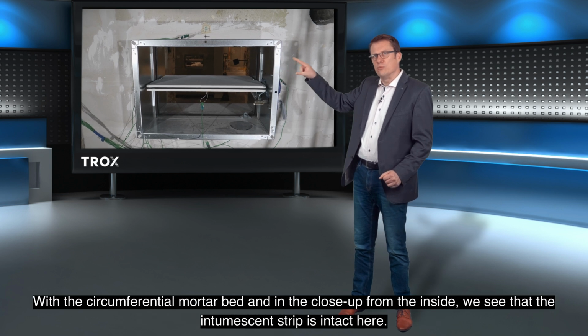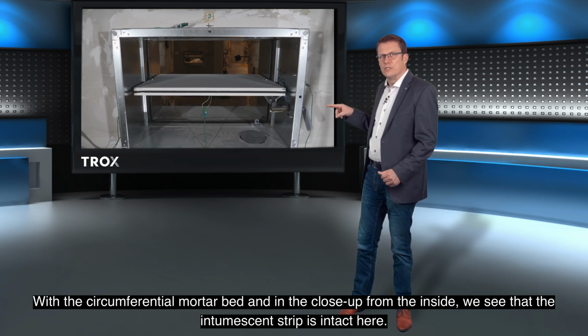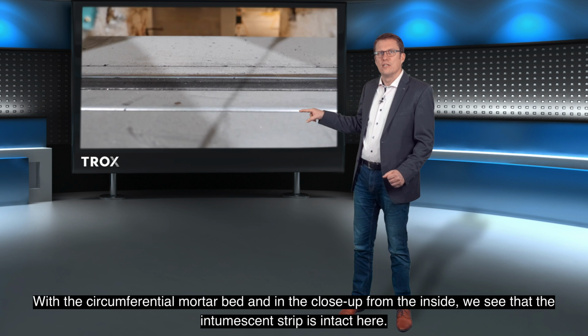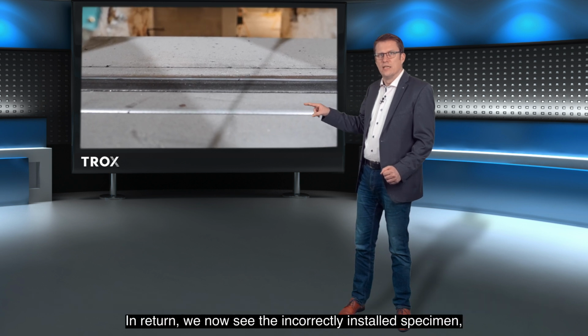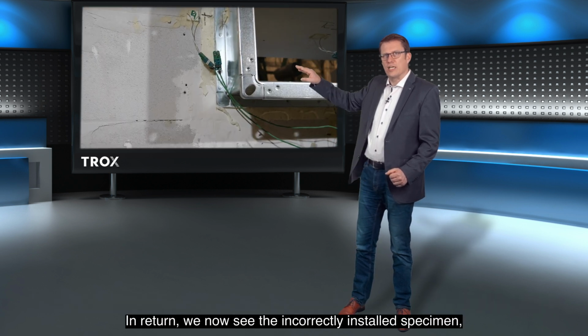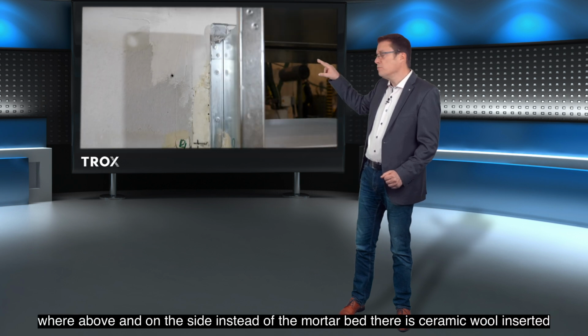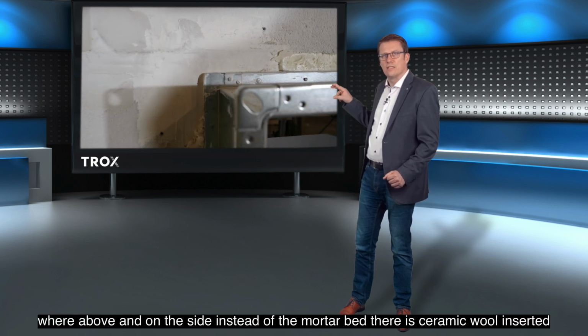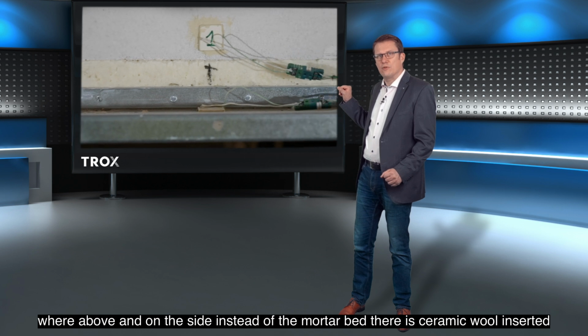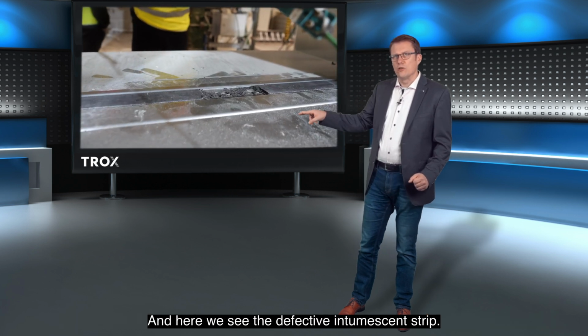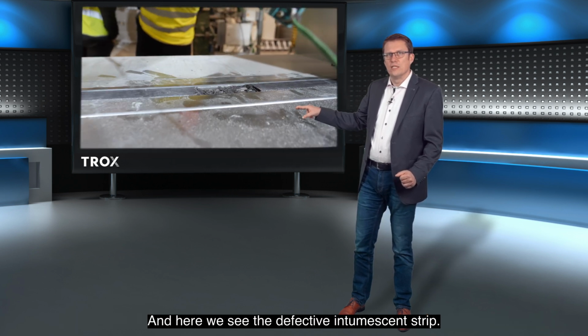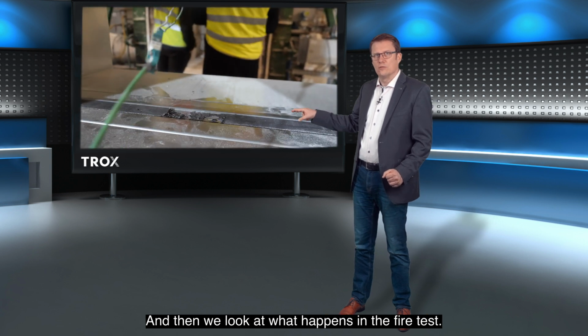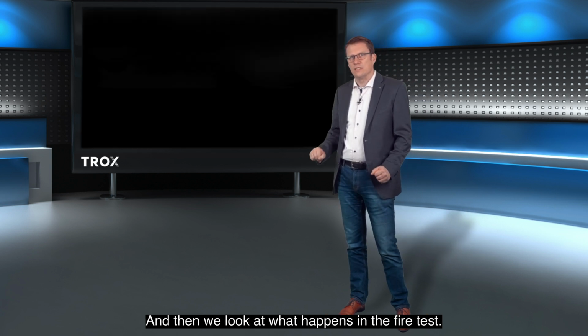Next, here is the pattern, which is installed correctly, with the circumferential mortar bed, and in the close-up from the inside, we see that the intumescent strip is intact here. In return, we now see the incorrectly installed specimen, where above and on the side instead of the mortar bed there is ceramic wool inserted. And here we see the defective intumescent strip, and then we look at what happens in the fire test.